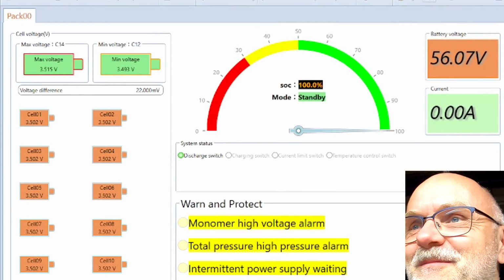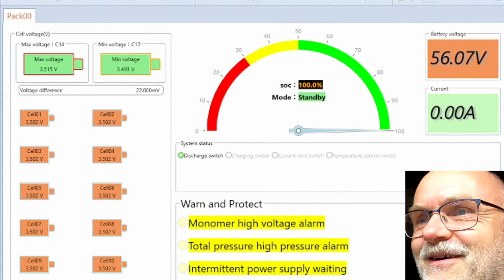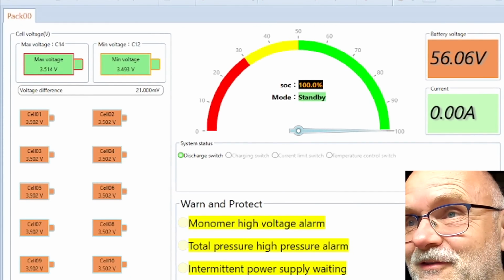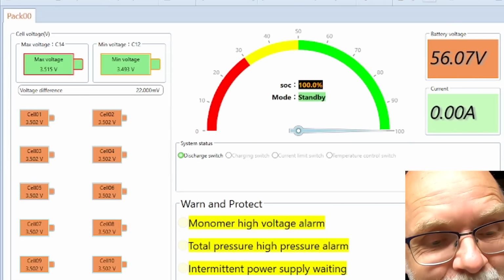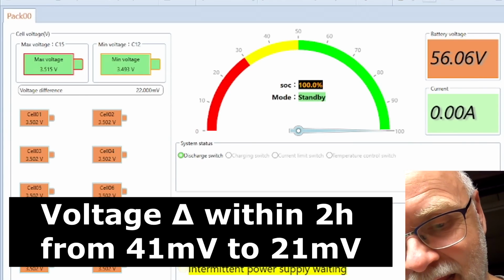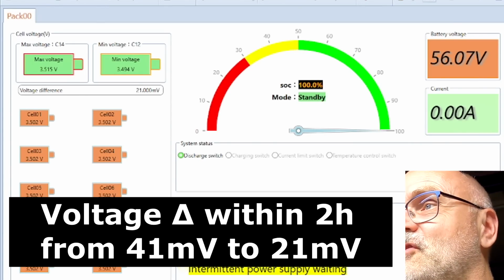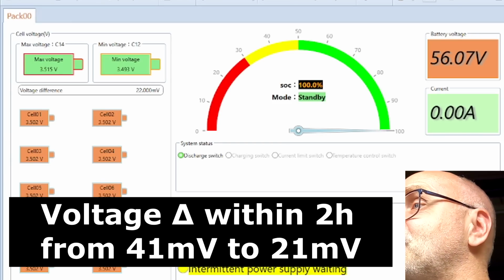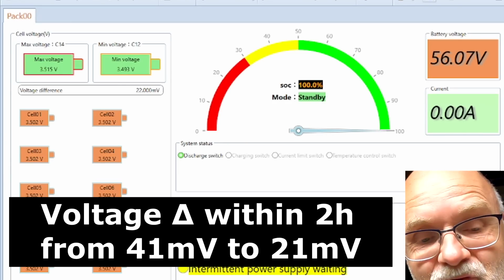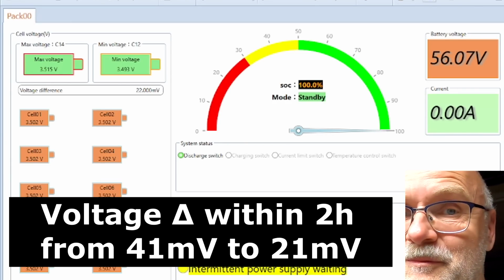Ooh, 21 millivolts only. So you can see we are still at 56 volts and the deviation has gone down from 41 at 6 o'clock to 21 millivolt at 8 o'clock. So in 2 hours, 20 millivolt. It is a very slow balancer, but it is balancing, very, very slow.